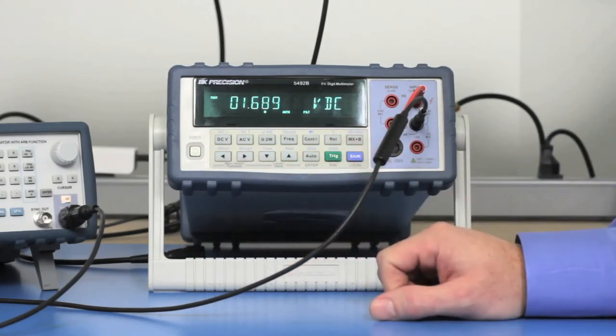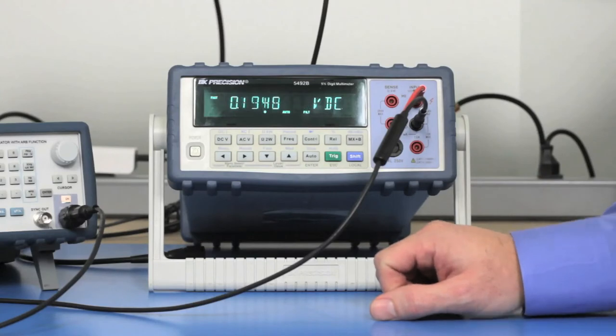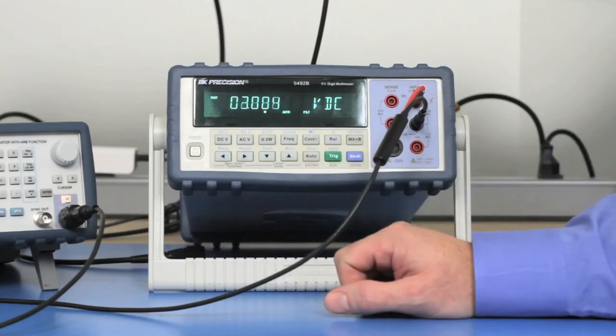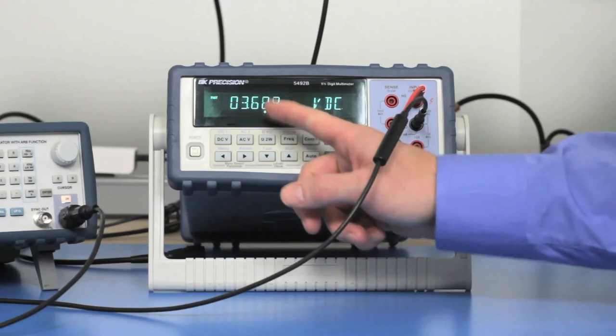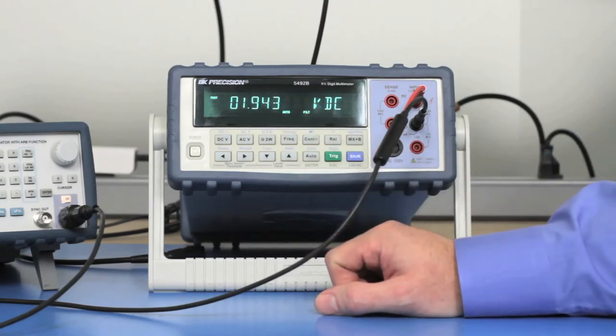As you'll see now, you're seeing all these readings, it's taking its measurements at 57 readings per second, and the asterisk is lit. As soon as the buffer is full, it will disappear, and we can go in and look at all of the values.